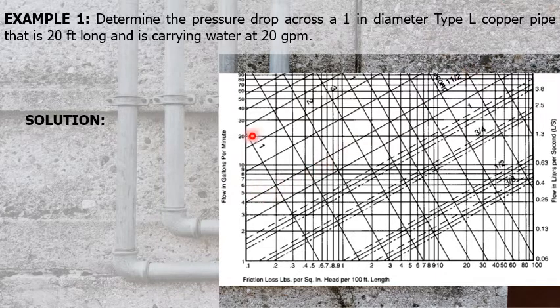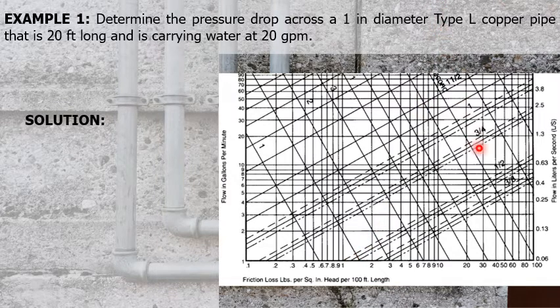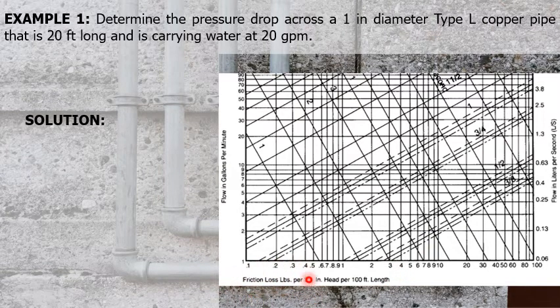Just a little background. On the left side of the chart, we have flow rate in gallons per minute. On the right side of the chart, we have flow rate in liters per second. On the bottom part of the chart, we have friction loss in psi per 100 feet length. These diagonal lines slanting downward from right to left are the diameters, and for type L, it is represented by the solid diagonal lines. To get the friction loss, we need first to locate the intersection of the flow rate in gallons per minute and the diameter.